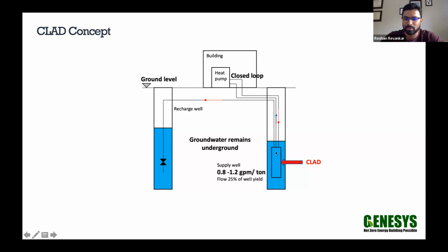The heat transfer happens in a water well. So you do need water, but all of the groundwater remains underground. The heat transfer happens inside the CLAD unit, and we will look at detailed design of this particular device. There is a pump at the bottom of the CLAD unit, a typical water well pump, which is pushing water through the CLAD unit in the opposite direction. So there is a counterflow happening here at the CLAD unit. This water is essentially activating the heat transfer on the closed loop side. It is a double wall heat exchanger, so there is no cross contamination of any sort, which also means that you could use antifreeze on the closed loop side.